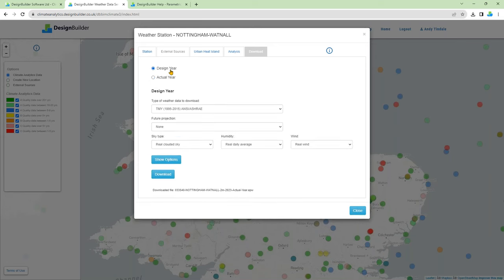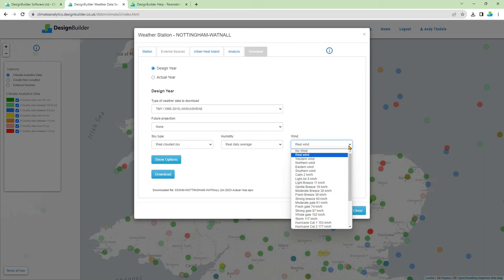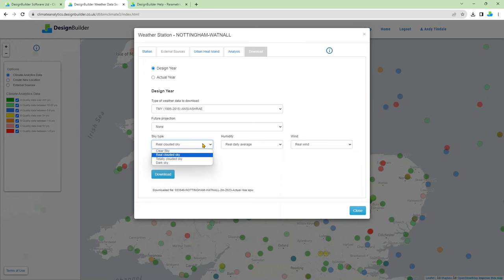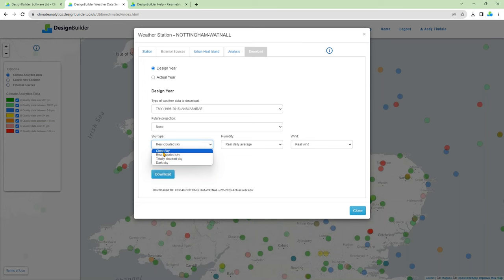Back in Climate Analytics, you can see the options to modify the design year data based on future projections, sky type, humidity and wind. There are also configuration options for more advanced users. Starting with the wind drop-down list: when simulating a natural ventilation system, the designer might wish to use a design file with no wind to ensure worst case scenarios are checked. Likewise, when simulations are being used for heating system sizing, we can select an option to generate weather data with no solar radiation to check that the heating design doesn't rely on solar gains. Or we can select an option to apply a clear sky scenario for worst case summer design simulations.